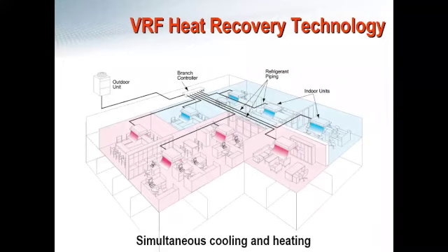So the second type of technology we have here is called heat recovery technology. Now, I know it looks very, very similar to the heat pump technology that we saw just a few slides ago, and that is actually the case. It is very, very similar, except for one component that is called out on this picture above. That's going to be our branch controller. So you're going to see that we still have the outdoor unit, all of your flexible refrigerant piping, and all of your indoor units serving their individualized zones, but the one additional component is that BC controller you see at the top of that picture. The way we like to think about the BC controller in simplest terms is that it's just a traffic cop. It's a component that's added to the system. It's full of sensors, linear expansion valves, and diverting valves.